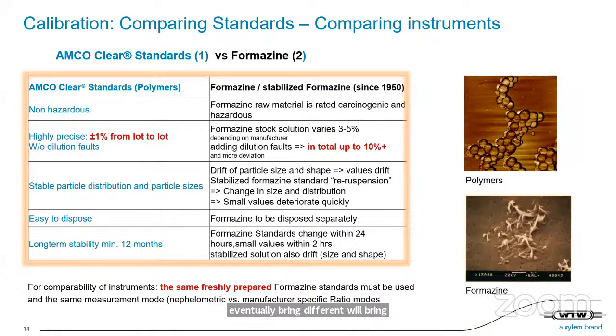And you must use the same metric, the same mode. So if one meter is measuring nephelometric, as we have seen before, the other instrument cannot measure ratio, because ratio is an internal algorithmic calculation of values. And this is giving a manufacturer-specific result.